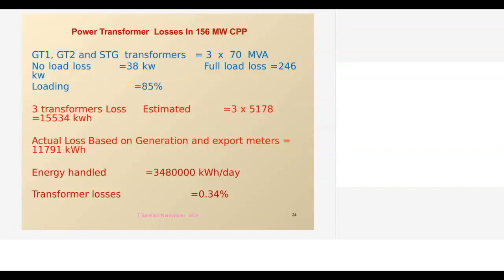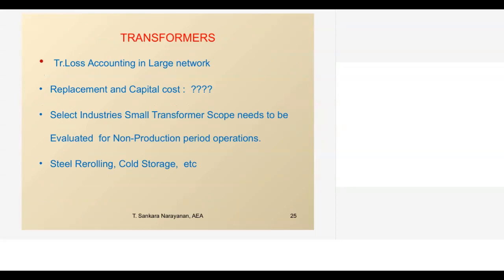For that, you have to connect the meter at least for 24 hours when the normal load is there in the plant. Then we can estimate the loss so that the distribution loss gap we will be able to reduce. So transformers, if we consolidate loss accounting in the large network, replacement is again a capital cost. So we have to wait for modernization of the plant, then I may do a replacement.